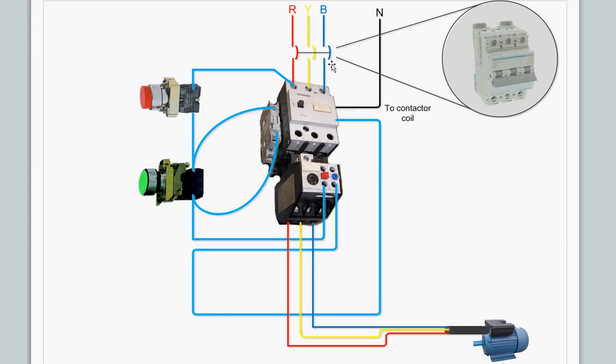So this circuit breaker, people can use the fuse or this circuit breaker here. Okay, so in this case, the contactor coil is 220 volt. So basically it gets the power here. It goes to the stop button, and then it goes to the start button, and it goes to this overload protection here. This is NC contact. I assume this is NC contact, normally closed contact. So it goes here, it goes this way, and then goes to the contactor coil here, and neutral comes directly to the contactor coil.